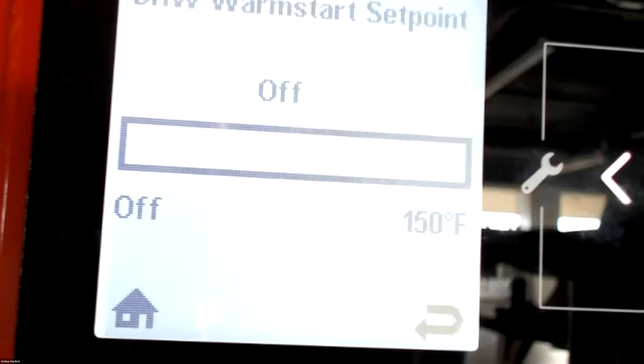Warm start, so I can enable this. It's going to come from the factory off. But if you want this boiler to keep that flat plate hot year round, this is where you can do that. And you can keep the warm start on and keep that flat plate, say 120 or 130, and solve any issues you have with that homeowner on the delay of hot water.